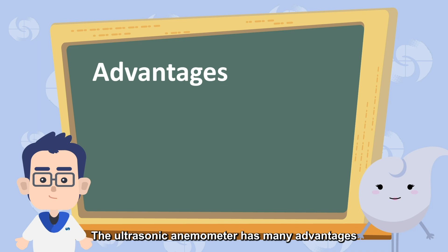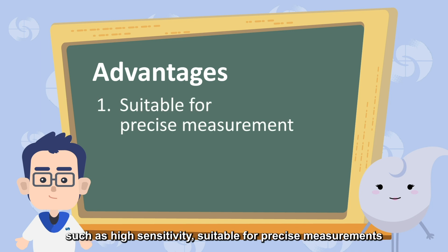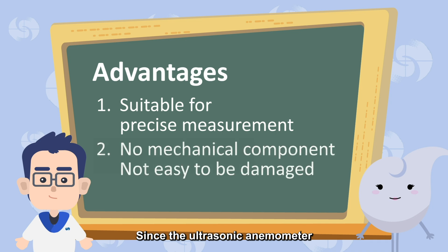The ultrasonic anemometer has many advantages, such as high sensitivity, suitable for precise measurements. In addition, when the wind direction changes drastically, it may cause damages to the mechanical components of the cup anemometer. Since the ultrasonic anemometer has no mechanical components, it is less likely to be damaged or worn.